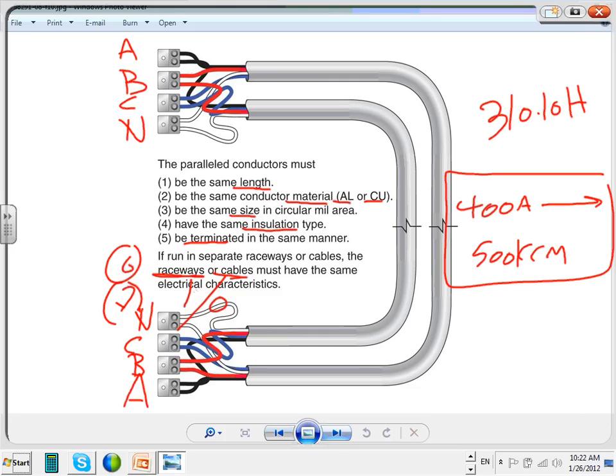So if I ask you, are phase A and phase B conductors parallel? Are they? No, only the 3 phase A conductors, 3 phase C, and 3 phase B, and the neutral. We don't parallel phase A with phase B, guys. That's a short circuit. You know what parallel is? You grab the end of the cable, tie it together at one end, and the other end you tie it together. Can you do that to phase A and phase B? You know what you get if you do that? Short circuit.